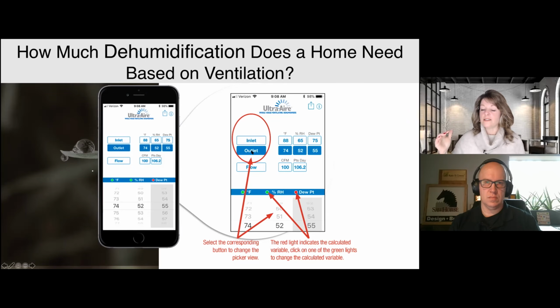The outlet is the temperature I want inside and the relative humidity I want inside. So I want 74 degrees inside, and I play with the RH number in order to get to that 55-degree dew point. So here I've just rolled it up and down a little until I see that 55-degree dew point automatically populate. And then the flow is my ventilation rate. So whether you're using 62.2 or whatever other standard, if you put in the CFM of your bath fan, you can put that in here. But whatever that ventilation rate is, it's going to tell you then, based on just ventilation alone and the conditions outside and what you want inside, how many pints a day of water removal you're going to need.